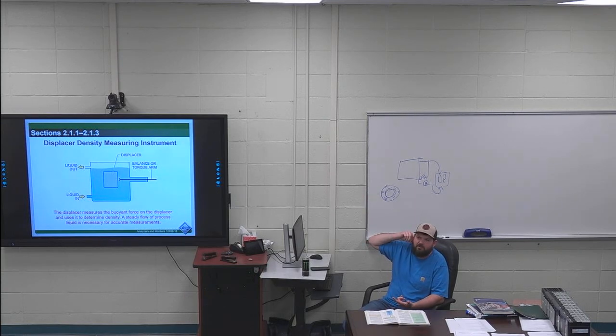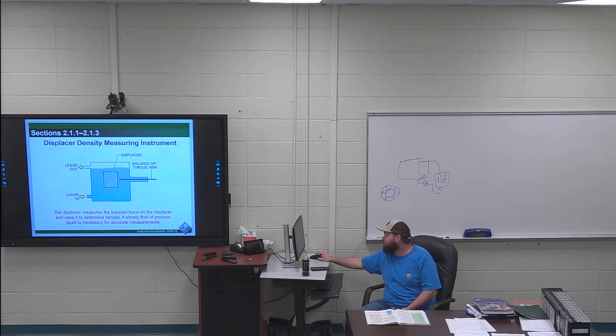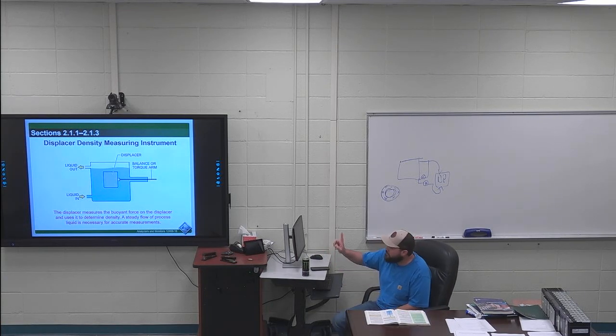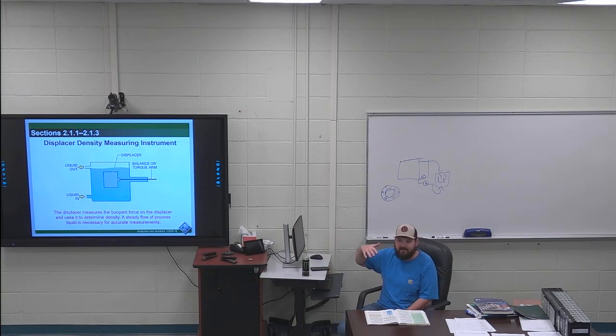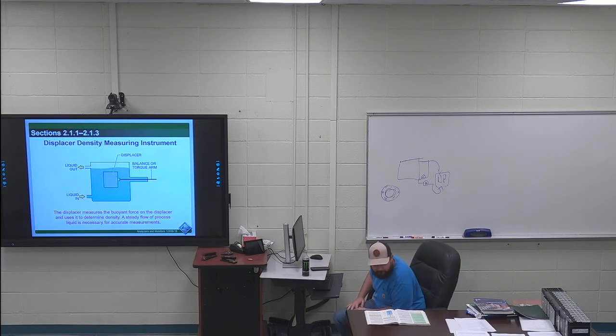Most everybody, if you've done the temperature labs in the back, I've pointed out the float for the hot water tank. That's a float. This displacer, a lot of people get this confused. This displacer doesn't move. It works on the principles of buoyancy. There is pressure pushing on the bottom of this, and it can take a force equation and tell a level measurement based on the amount of force pushing on the bottom of it, rather than actually moving. There's probably going to be a little bit of movement, but not like a float moving up and down.